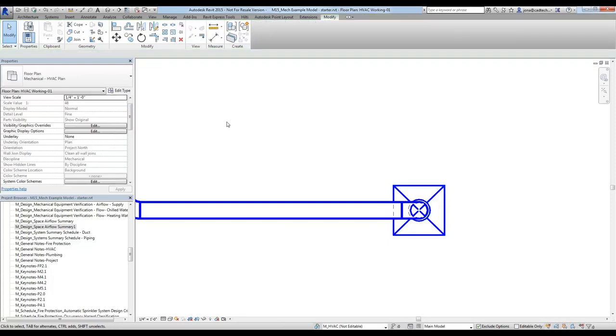Another question just came in. What issues do you typically run into when exporting the GBXML, and how do you address them? The biggest issue I've run into is the size of roof that happens to be over a space. Typically, we'll just manually fix that.